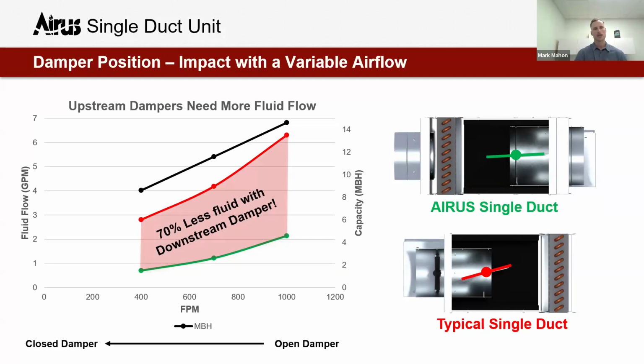One question was, does it increase the bypass through the coil as well? So I'm thinking we're discussing airflow bypass through the coil. All of the testing that we have done is assuming the same supply airflow rate at the inlet, targeting the same capacity and leaving air temperature. We actually have CFD analysis on the product that is going to be finalized by the end of this week. That might be able to pull back the curtain on that a little bit further. But broadly speaking, I would say no, at least not to a point that it would impact performance that's measurable in a lab.